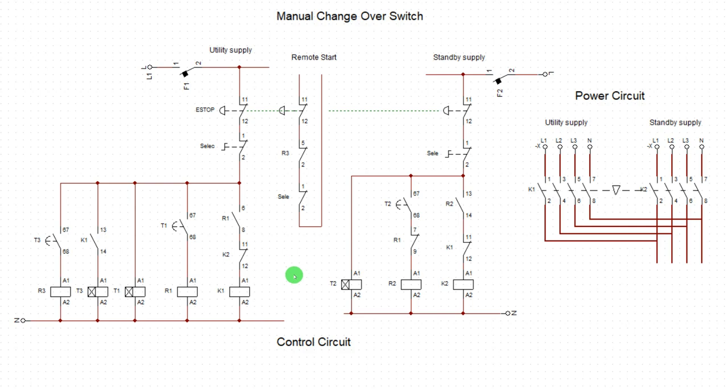Then another one again, when you start the genset, you now discover that the cool down duration is there already. Check how many minutes that is there. If it is 3 minutes and you don't know how to remove it, you don't know how to change it, that is not an issue. Leave it with the default 3 minutes. All you need to do is to come to your ATS, disable this, take this timer, put it on 0 so that it does not time.